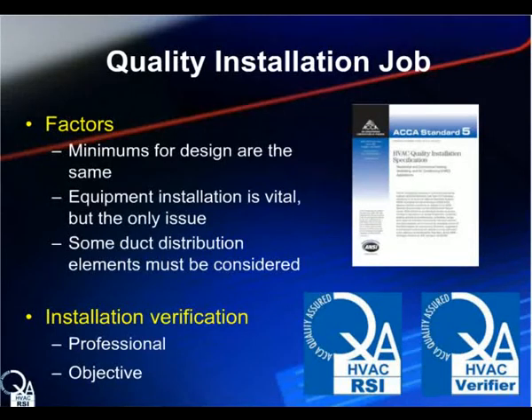Designing the heating and cooling loads according to Manual J is accepted as minimum code, as is equipment selection according to Manual S. More and more contractors ensure their technicians check the refrigerant charge, airflow, and that combustion appliances are operating properly. A QI job, though, goes further, ensuring the distribution system meets specified metrics and the system is tested and certain measurements are recorded.